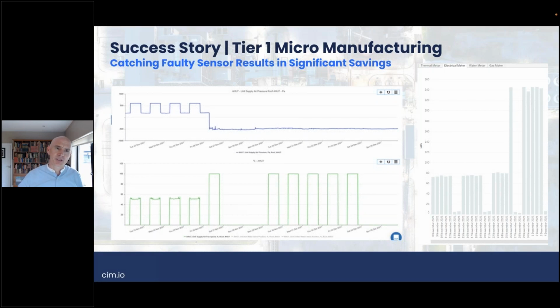This is a static pressure set point, a static pressure sensor in the field, and it was reading anywhere between 500 and 620 pascals, but it became faulty at this point here and started reading a much lower pressure in the duct. As you can see, the BMS then reacted and brought the supply fan from 50% speed, which was running on the VSD, up to 100%. The reason it's turning on and off is that the night mode and the weekend mode were still operating. But when it did come on, it was still running at 100%, even though it wasn't making any difference to the supply pressure in the duct.